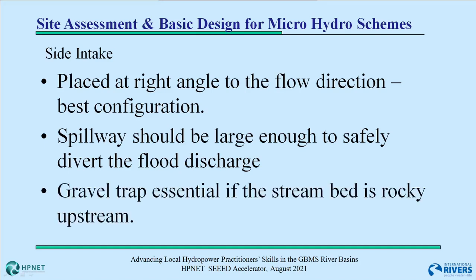If the stream bed is rocky, then there will be a lot of small loose stones which will roll down. So it is an absolute necessity to have a gravel trap which will make the stones settle down. If it is not done, these stones may enter into the turbine and damage the turbine.